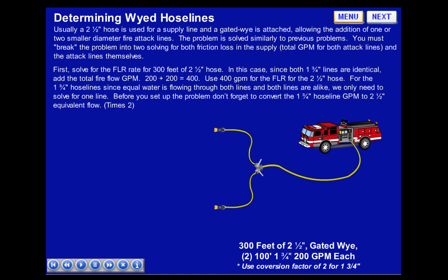First, solve for the friction loss rate for 300 feet of 2.5-inch hose. Since both 1¾-inch lines are identical, add the total fire flow GPM: 200 plus 200 equals 400. Use 400 GPM for the FLR calculation for the 2.5-inch hose.